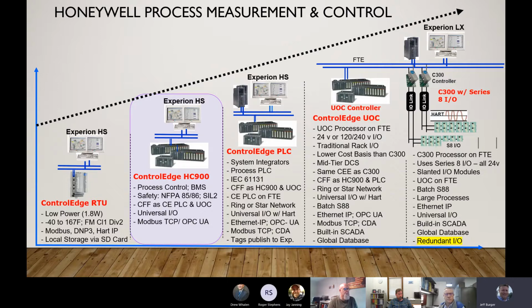It has a universal I/O, so it allows you to configure the I/O card for inputs and outputs. Universal in the sense of being able to choose between many different thermocouples, RTDs, voltages, milliamps, and it allows for a nice compact card that has all the different types of inputs and outputs. This system will also communicate Modbus TCP, also OPC UA.